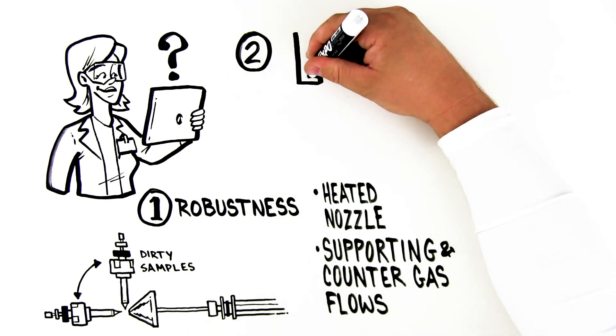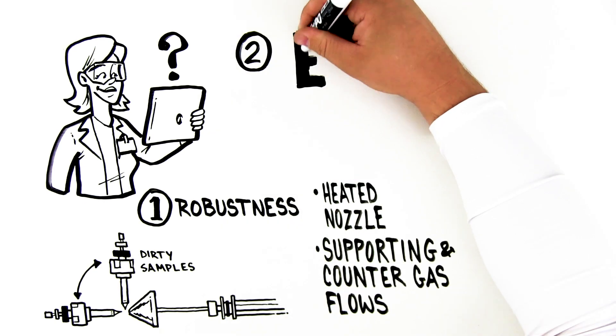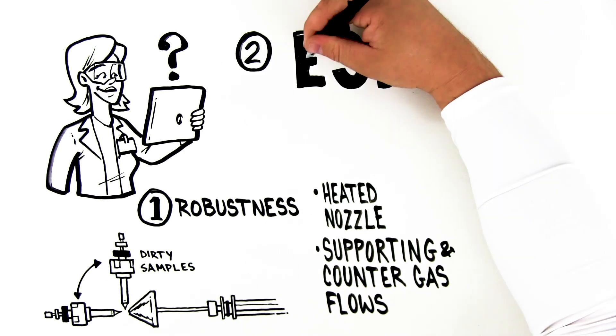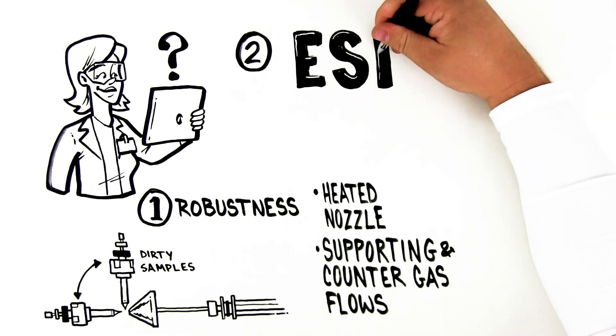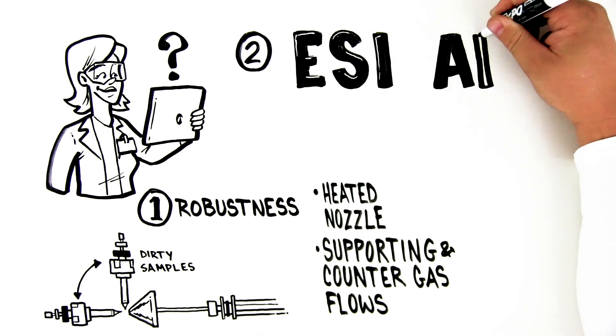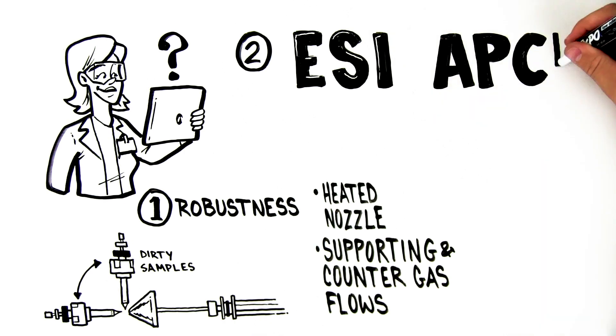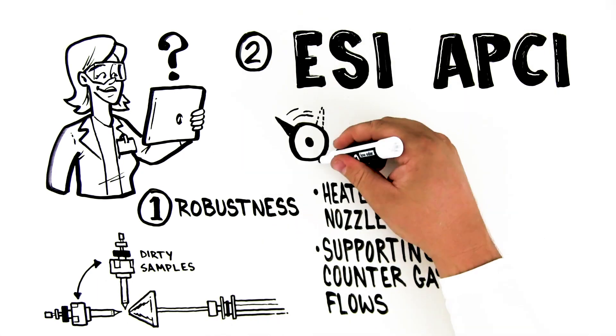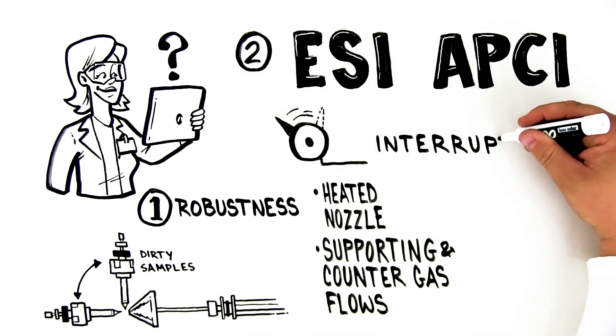Second, the compounds that can be detected depends on the ion source. Electrospray ionization is suitable for polar, relatively labile compounds. Atmospheric pressure chemical ionization is suitable for low or medium polarity compounds. An instrument that allows easy switching between these helps Jenny prevent workflow interruptions.